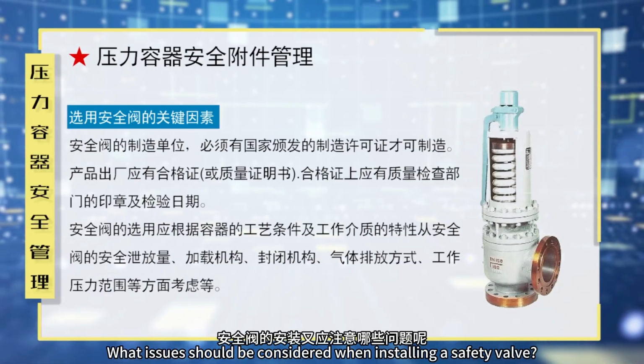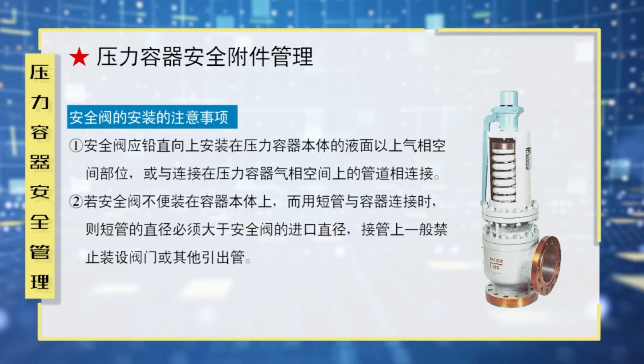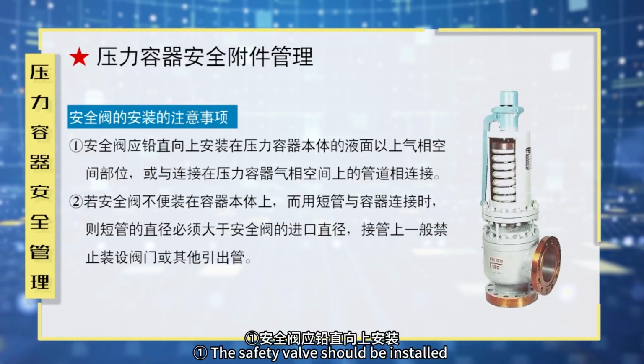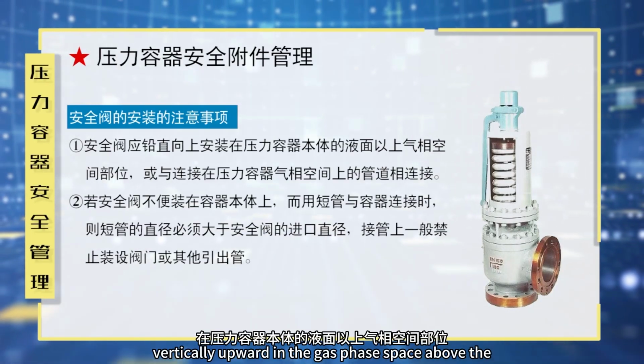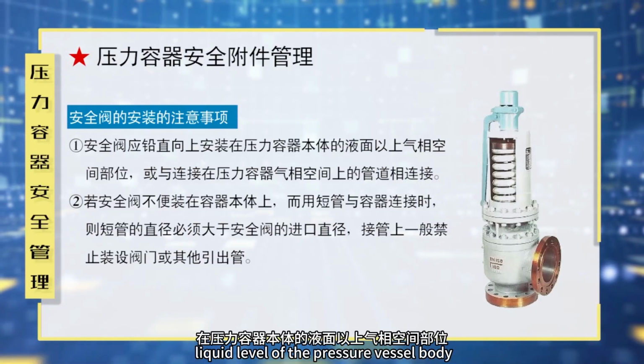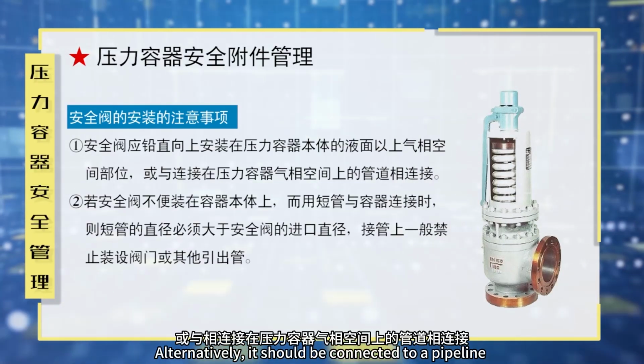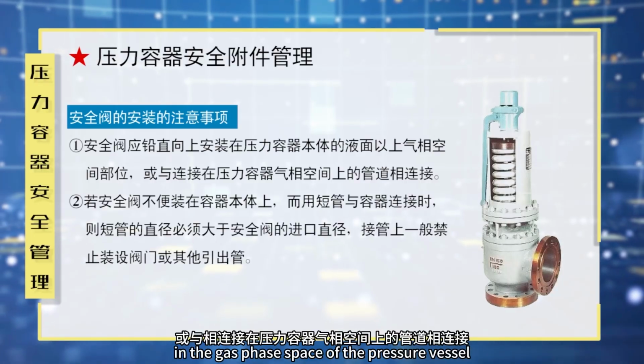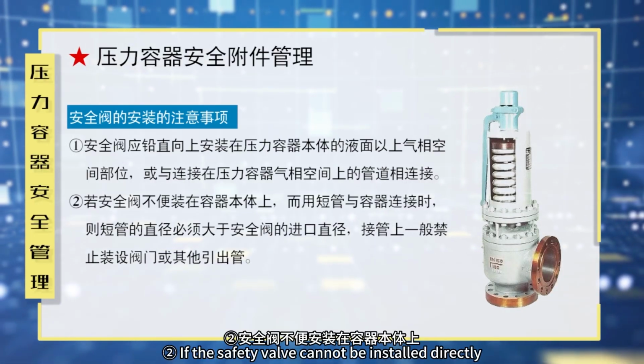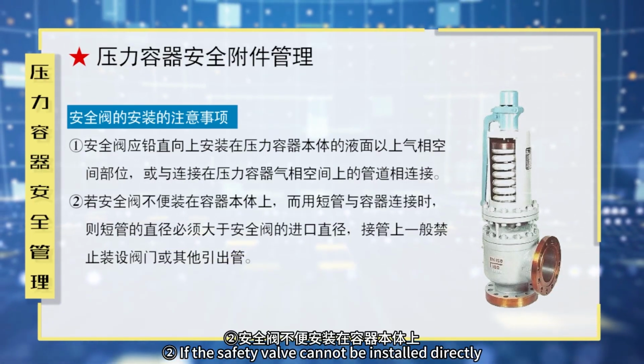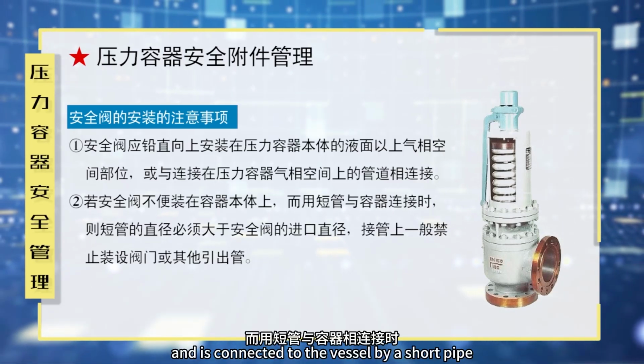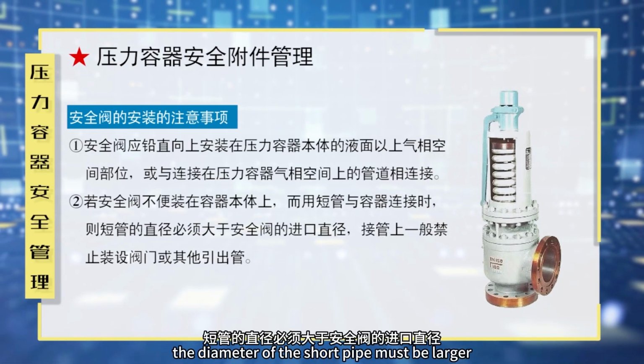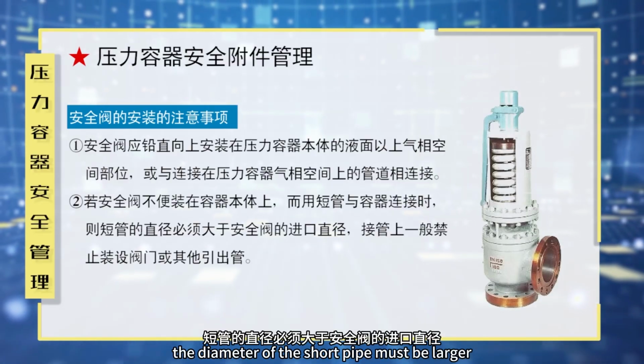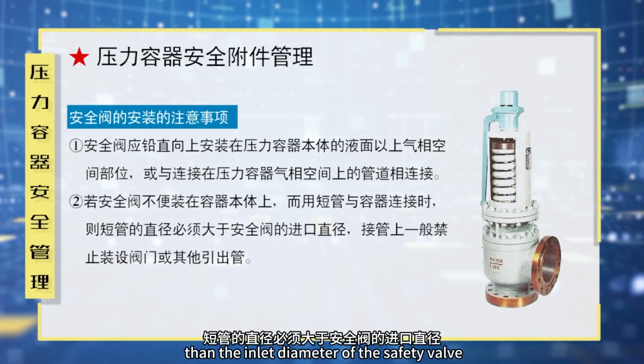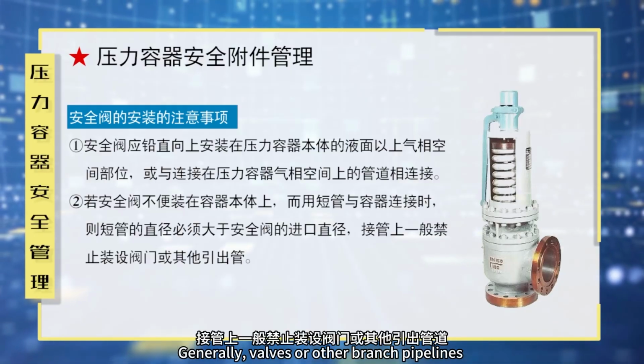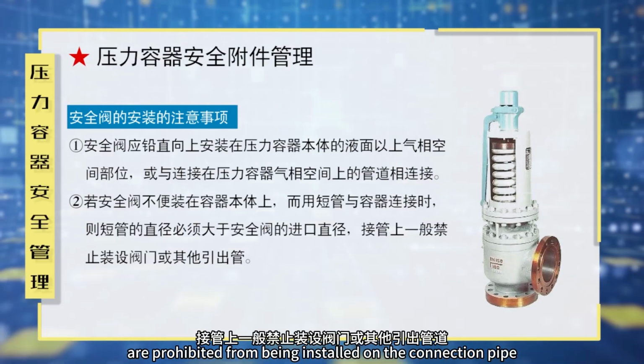What issues should be considered when installing a safety valve? First, the safety valve should be installed vertically upward in the gas phase space above the liquid level of the pressure vessel body. Alternatively, it should be connected to a pipeline in the gas phase space of the pressure vessel. Second, if the safety valve cannot be installed directly on the vessel body and is connected to the vessel by a short pipe, the diameter of the short pipe must be larger than the inlet diameter of the safety valve. Generally, valves or other branch pipelines are prohibited from being installed on the connection pipe.